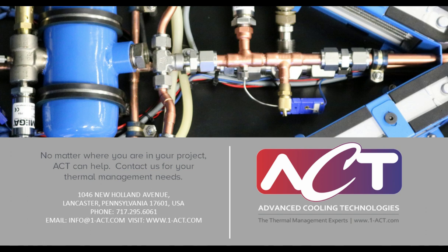That's a good question. In fact, it is. The saturation temperature in a pumped two-phase system can be controlled by the temperature at which you condense the fluid. For instance, if you have a condenser that's liquid cooled, and you set the condenser temperature to your desired component temperature, the fluid inside of the loop of a pumped two-phase system will operate at that temperature. If you adjust the temperature of the condenser, you can adjust the saturation temperature of the loop, which will adjust the temperature of your component. So it's relatively straightforward to adjust the operating temperature of a pumped two-phase system just by changing the temperature at which you condense the fluid.